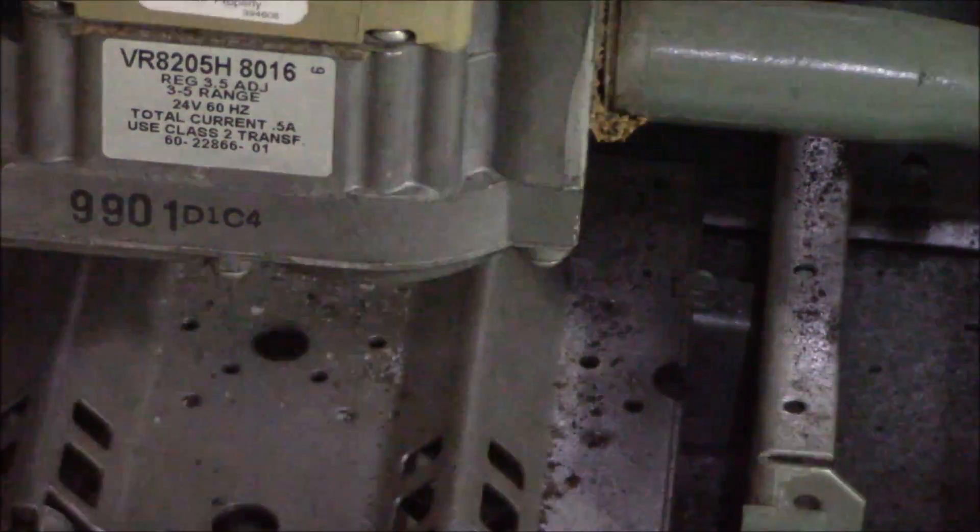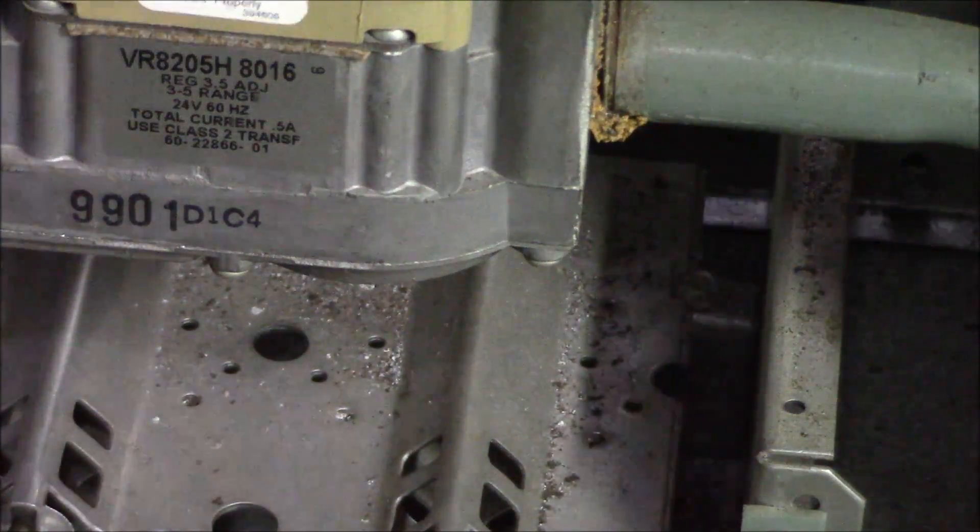Right there, those little quarter inch screws like that will hold that burner plate in. One, two, three, four of them removed and you'll have the burner out and can clean it. Be very careful - hot surface igniters are very sensitive to touch and drop. If you drop it, you break it. Touch it, you break it. Bump it, you break it. Anything other than just sitting there or in a nice padded box, can you guess what's gonna happen? You broke it.